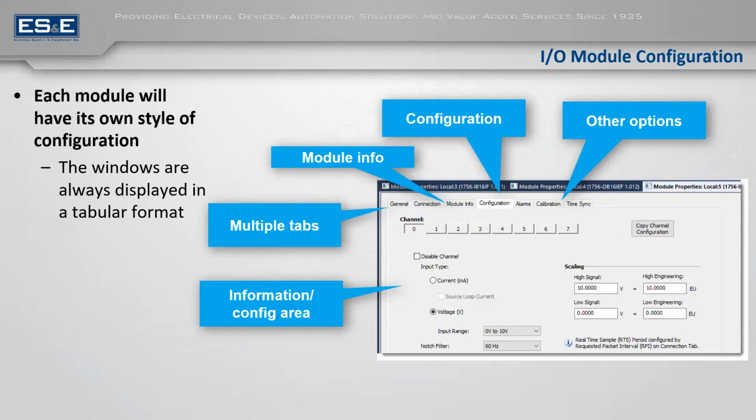The connection tab, the next one over, is where you have the ability to inhibit, which means you can tell the controller, do not look for that device. That comes in useful if you know that you are going to fault a controller by pulling some sort of device. With CompactLogix and ControlLogix, you can remove or exchange cards and nodes while powered up.